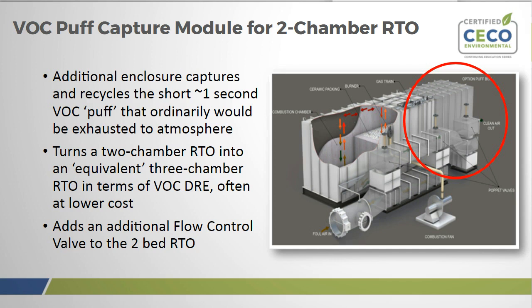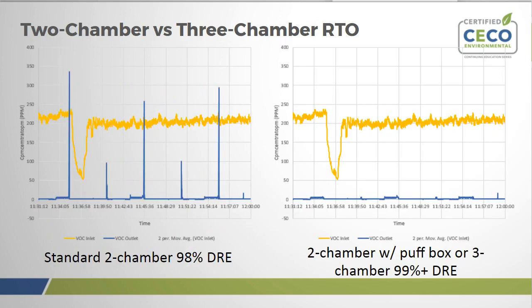So here we have an example. Hopefully this helps for those who like seeing graphs. We have the difference between a standard 2-chamber on the left, and a 3-chamber, or you could say a 2-chamber with a puff box, on the right. The yellow line indicates VOC inlet concentration, and the blue line indicates the outlet. For the most part, you could think of destruction efficiency as 1 minus the area under the blue curve divided by the area under the yellow curve. Those spikes you see in the blue are the VOC puffs. So every 4 minutes, give or take, depending on how you set it up, you have a VOC spike. In the case of the 3-chamber or the 2-chamber with puff capture box, you eliminate that spike and you oxidize close to 100%. And so that's where you can get those really high destruction efficiencies if it's required.